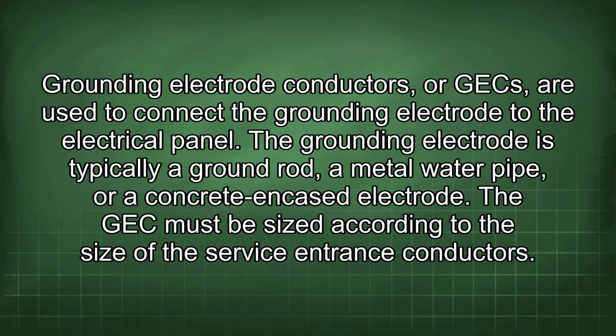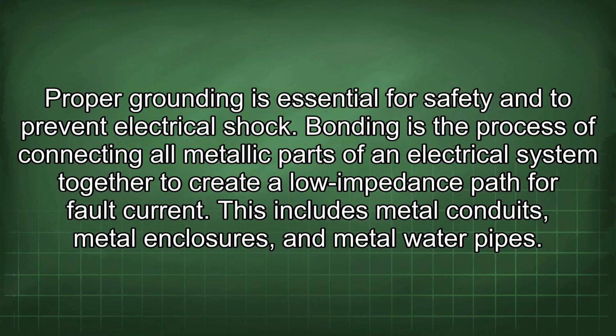Grounding electrode conductors, or GECs, are used to connect the grounding electrode to the electrical panel. The grounding electrode is typically a ground rod, a metal water pipe, or a concrete-encased electrode. The GEC must be sized according to the size of the service entrance conductors. Proper grounding is essential for safety and to prevent electrical shock.